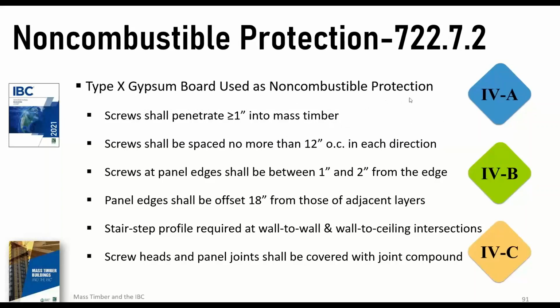So if we're using non-combustible protection as gypsum wallboard, we have to have very detailed provisions for the type of screws, the material, the construction, the threads, everything else, how the joints are lapped, what the fastener schedule is, what the penetration is. These are all very, very detailed aspects of the installation in terms of drywall screws. So when you get into the actual code change provisions, you'll see that type S screws are typically called out in the specifications. Type S, or steel or self-drilling tapping screws, are commonly associated with attaching gypsum to steel studs, versus a type W screw would typically be associated with driving a screw into a wood substrate.